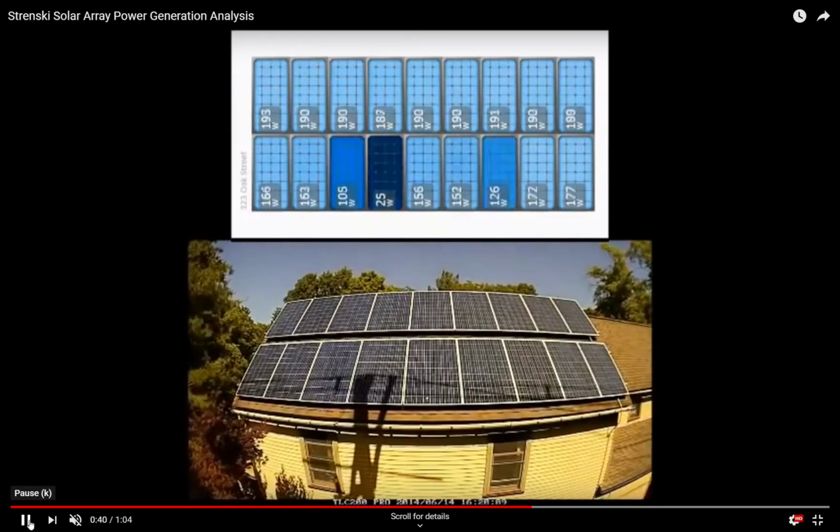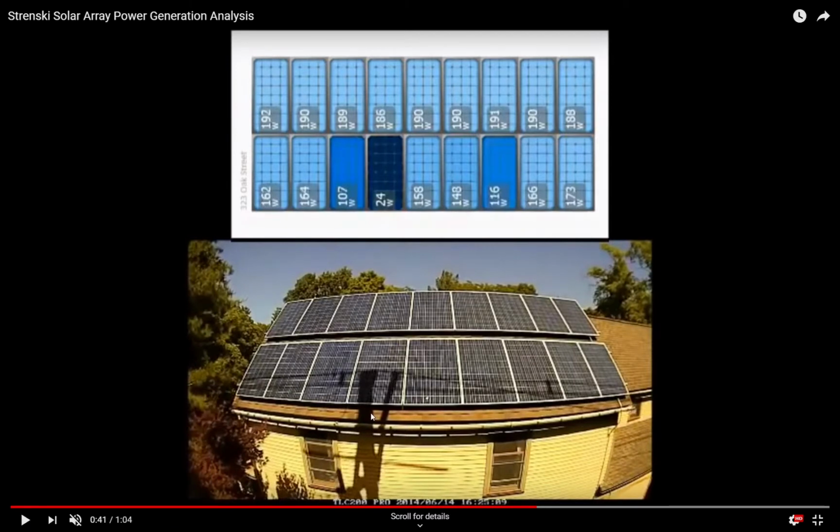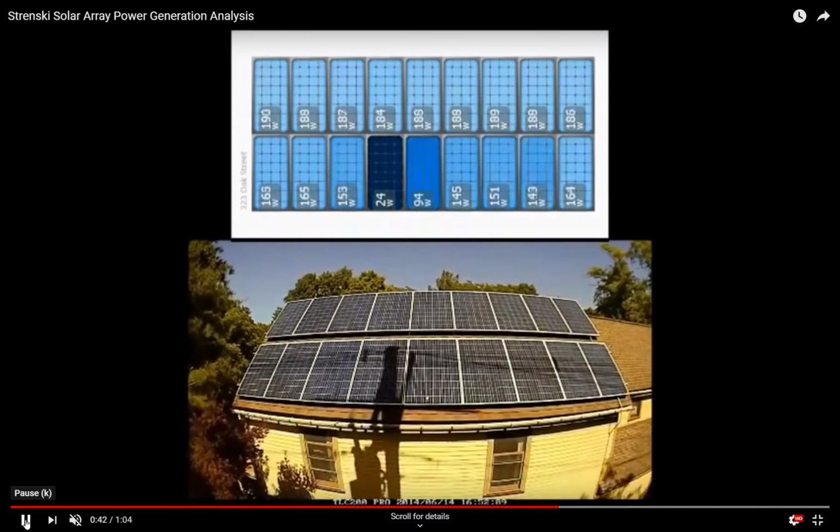So we've got a power line in the area that is now casting a shade over the modules, and we're starting to see some of the panels take effect. And we've got this module here, 24 watts. Now, if this was a string system using standard DC technology, these modules would only perform to the strength of this one module here, that 24 watt module. So you wouldn't have this 192, 190 and so forth. So you'd be losing a lot of power, as all these would ramp down as they all wired together. So this is where microinverters really come to the fore here.